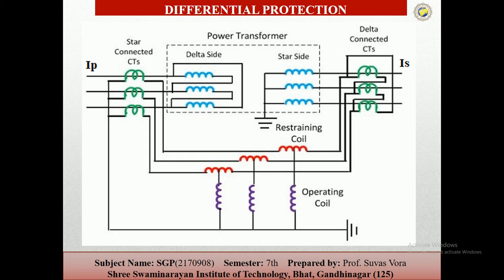The working of the percentage relay is that the torque due to the restraining coil prevents the closing of the tripping circuit, while the torque due to the operating coil tends to close the tripping contacts. Under normal operating conditions, the torque developed by the restraining coil is greater than that of the operating coil, and thus the relay remains inoperative. That is, the operating coil has less energy than the restraining coil under normal conditions.